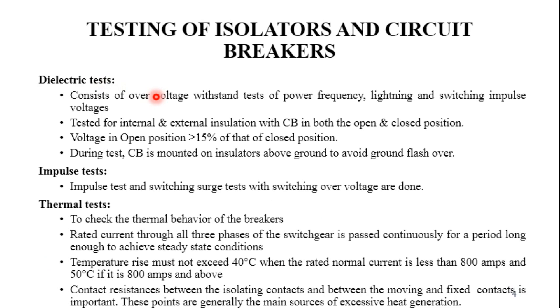To assess these factors, the main tests conducted on breakers and isolator switches are: the dielectric test or overvoltage test, the temperature rise test, the mechanical test, and the short circuit test. The dielectric test consists of overvoltage tests at power frequency, lightning impulse, and switching impulse voltages. It is tested for both internal and external insulation of the circuit breaker in both open and closed positions.